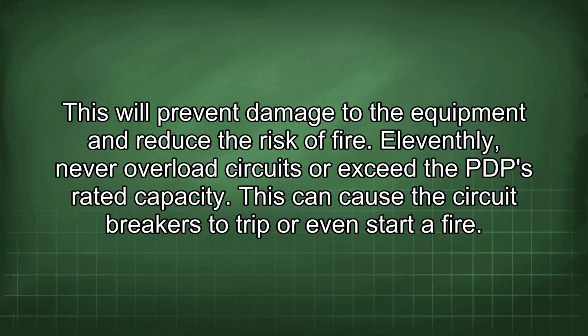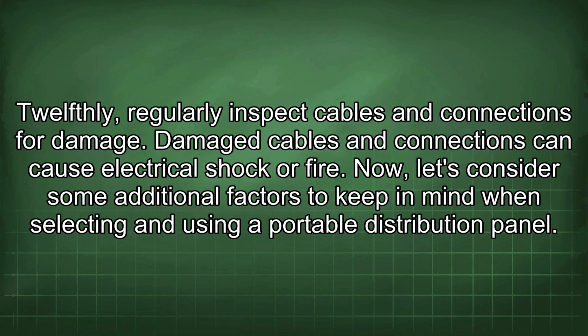Eleventhly, never overload circuits or exceed the PDP rated capacity. This can cause the circuit breakers to trip or even start a fire. Twelfthly, regularly inspect cables and connections for damage. Damaged cables and connections can cause electrical shock or fire. Now, let's consider some additional factors to keep in mind when selecting and using a portable distribution panel.